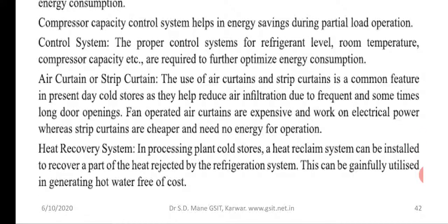Then the air curtain. I think I have seen one cold storage where the air curtain or the plastic strip curtain was also not proper. So a lot of cold air leakage was there. That kind of thing should not happen. You should take care of that. This is very simple common sense that we can see.